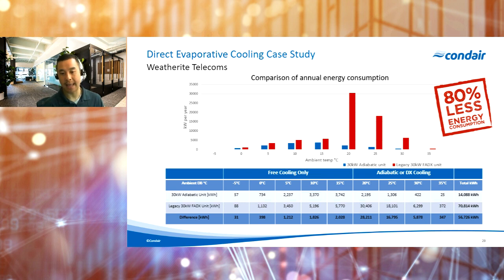You can see here anything less than about 20 degrees C, both systems, the legacy DX cooling unit and the 30 kilowatt adiabatic unit, would be operating in free cooling mode only. Above 20 degrees C, depending on the system, we would either be operating in adiabatic cooling mode or in DX cooling mode. The next two rows show the cumulative energy consumption, which is calculated based on the number of hours out of the year at that ambient condition and the operating mode. So we're effectively comparing both of these throughout the year, looking at those specific operating modes and the hours that they are operating within those modes.